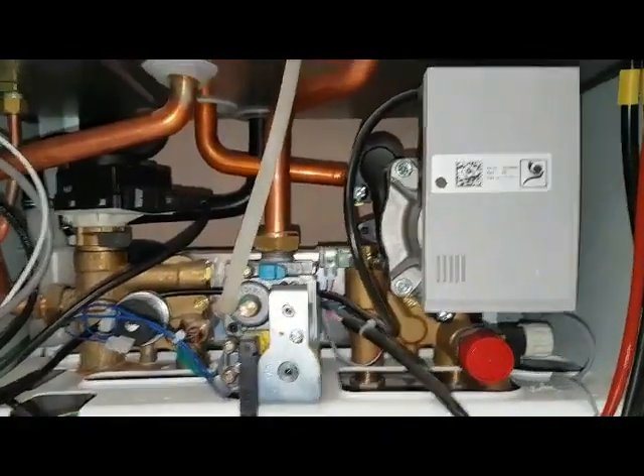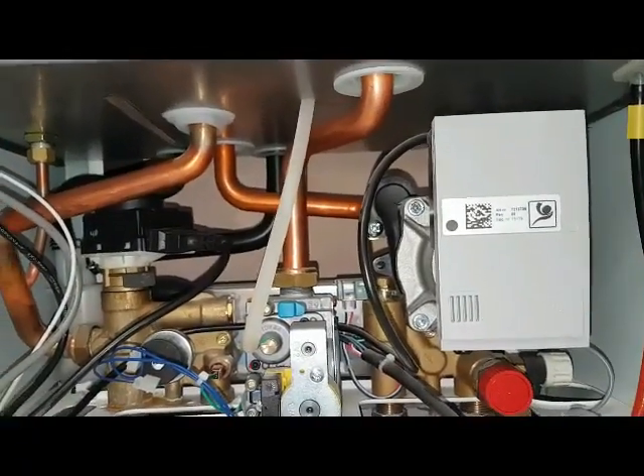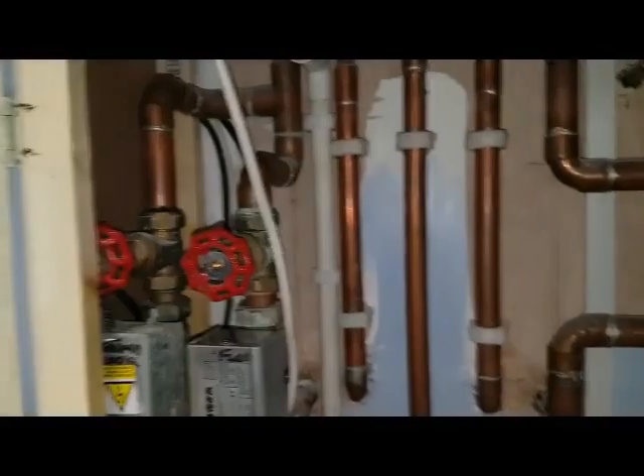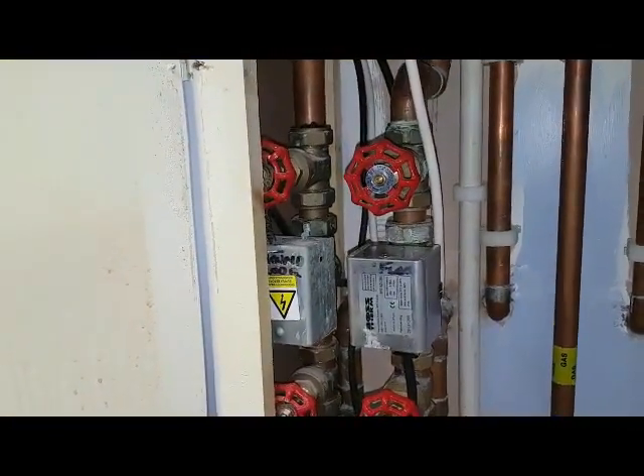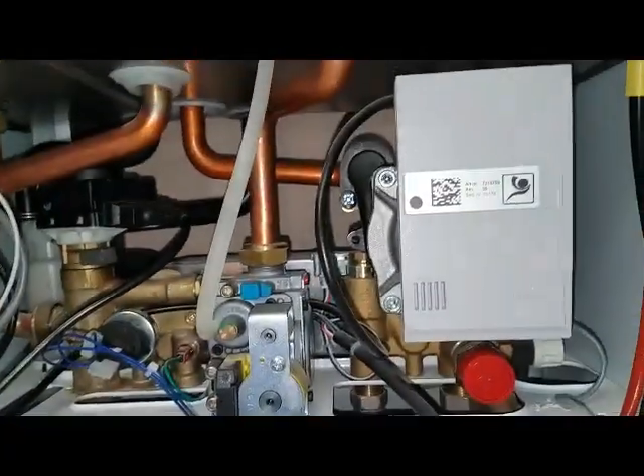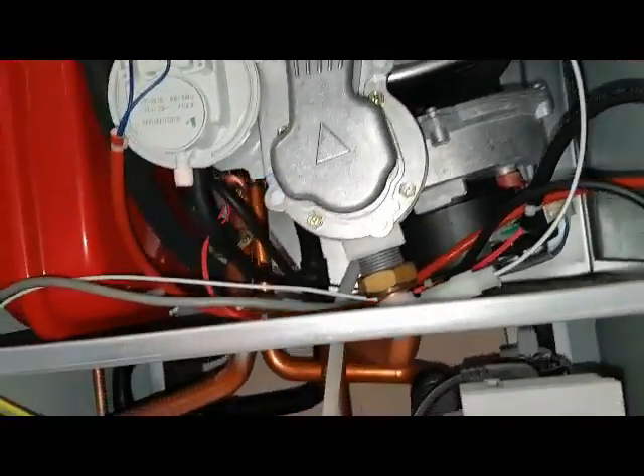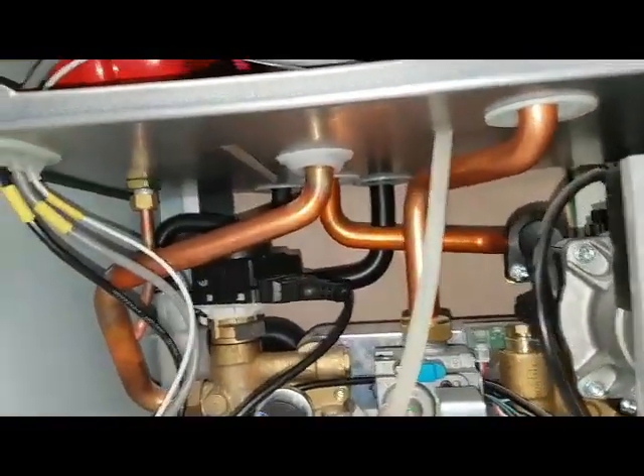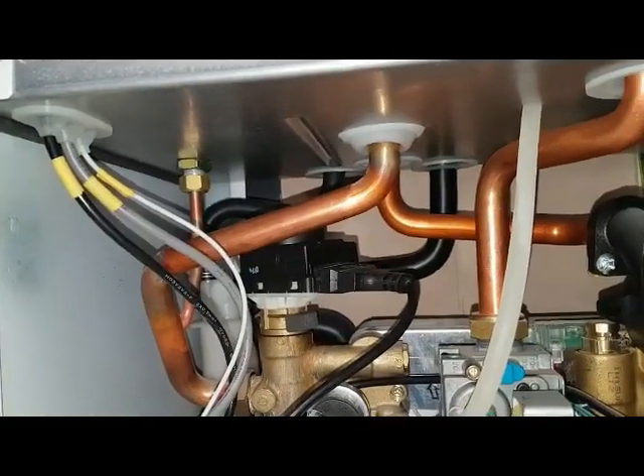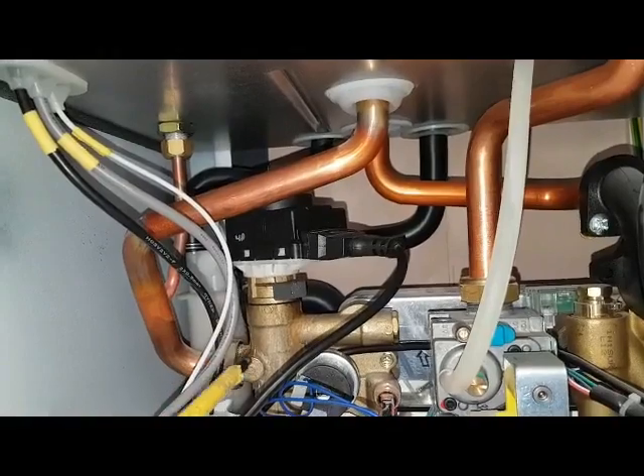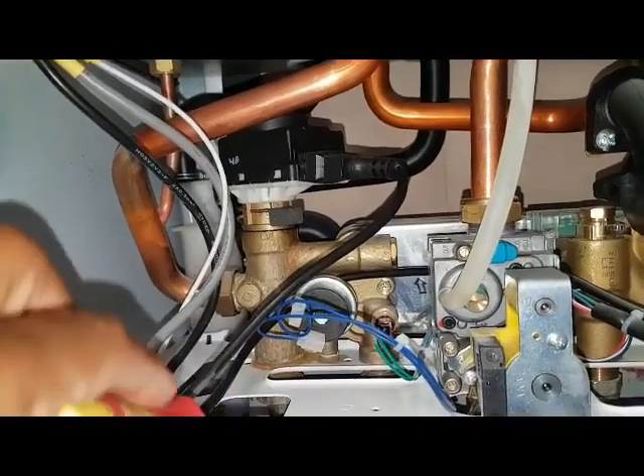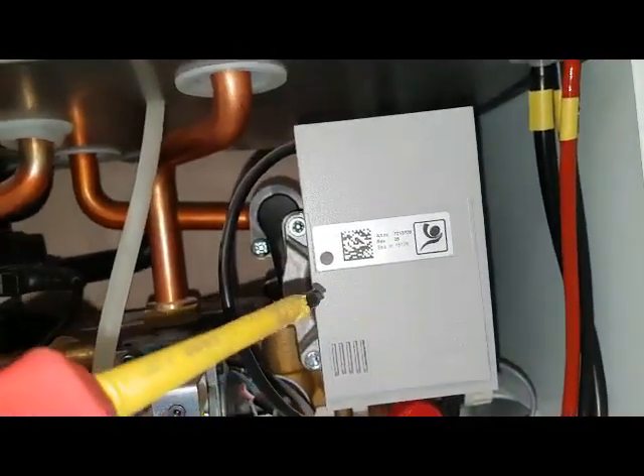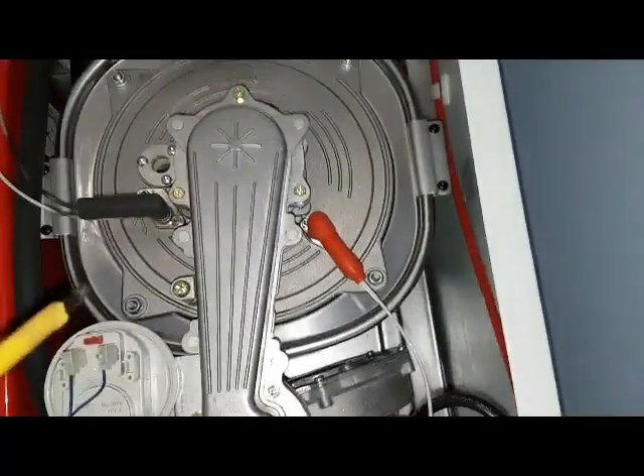On the heating side, you've got a demand put on it by the room thermostat. These zone valves will be putting a demand on as well. Starts the pump. Pump runs. Fan runs. Basically the same thing, really. The only difference is when it comes down here, it goes back on the sequence. It's going to go down this flow and out to the radiators. And then just return back on the return pipe, back into the pump, up, gets heated, back down again, around the system.